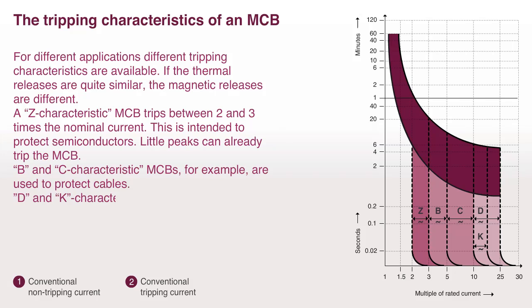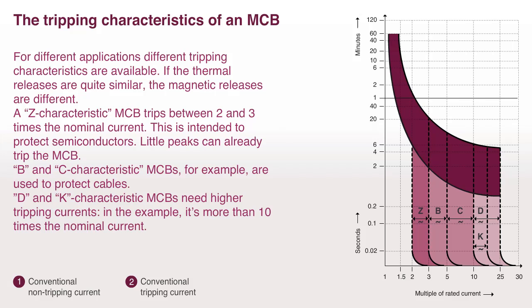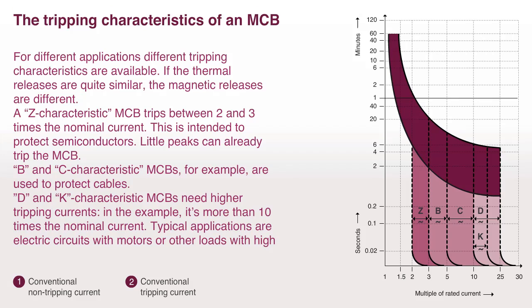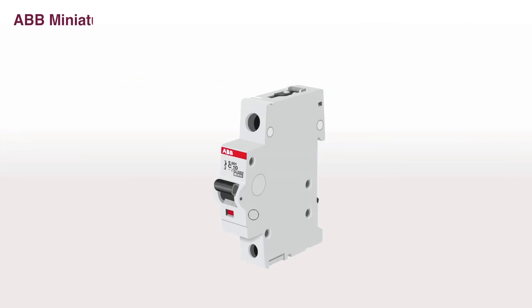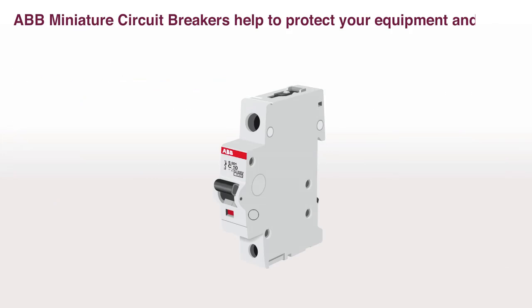D and K characteristic MCBs need higher tripping currents — in the example, more than 10 times the nominal current. Typical applications are electric circuits with motors or other loads with high start-up currents. ABB miniature circuit breakers help to protect your equipment, and therefore your property.